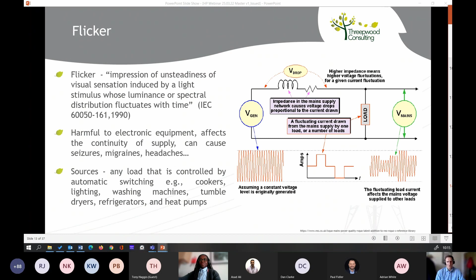You mentioned the impedance, and why that's important when you're determining what flicker is. Can you tell us a bit more about how impedance is managed when you're assessing for flicker? The reason why DNOs aren't called all the time by customers complaining that their lights are flickering is because they are able to keep a lid on this using one of the standards my colleague mentioned, 61000-3-3. Devices are tested to a specific impedance, ZREF, which was obtained by an averaging technique for multiple utilities. If you pass the limit specified in 61000-3-3, you can connect to the supply. However, if devices fail, they are subjected to conditional connection. So ZREF is the benchmark for unconditional connection.